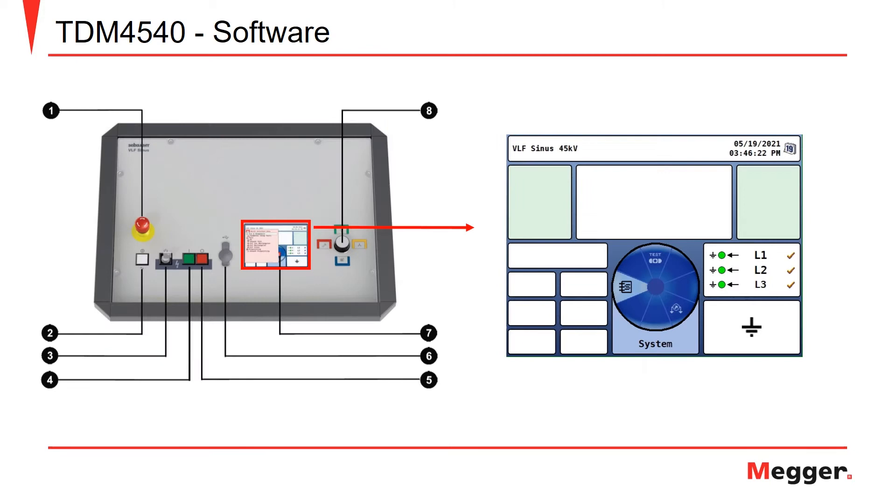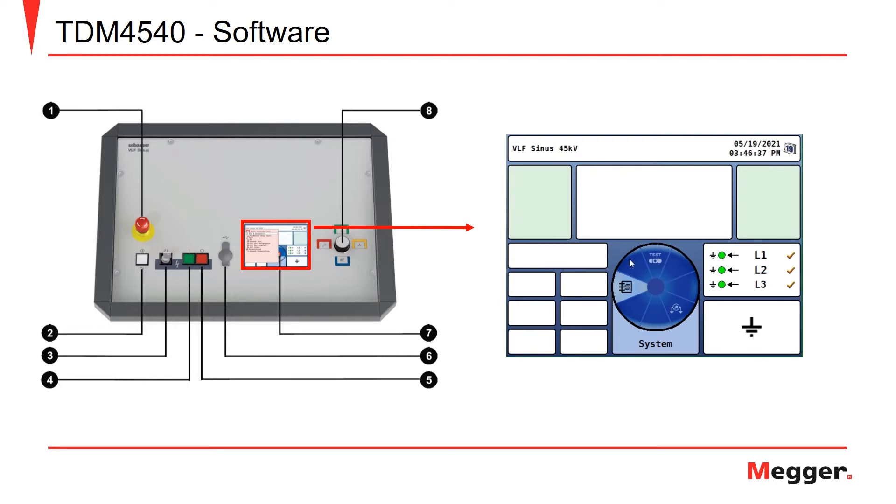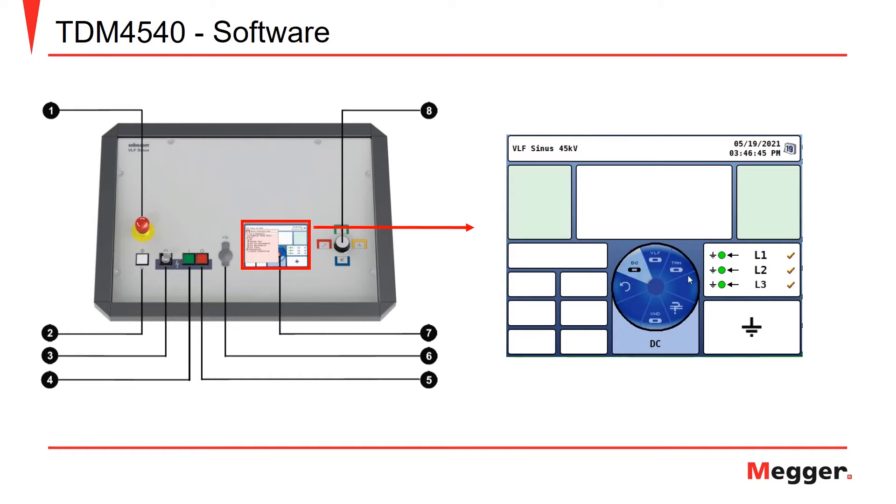Here we can see the example of the home screen for the TDM45 or TDM4540, and for the purpose of this video, we're going to use this demonstration to perform a tan-delta test. On our pinwheel selection, we will click the test option, and within the test option, we can see we can perform DC testing, VLF testing, tan-delta testing, sheath testing, and withstand testing as well. Let's choose the VLF tan-delta testing.